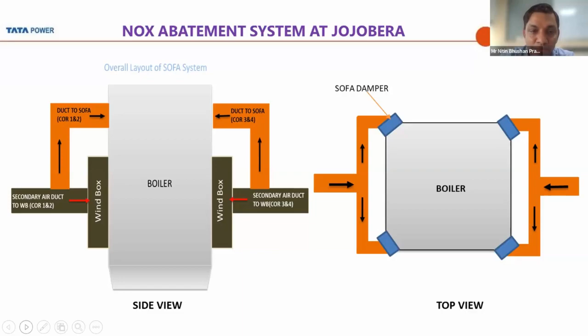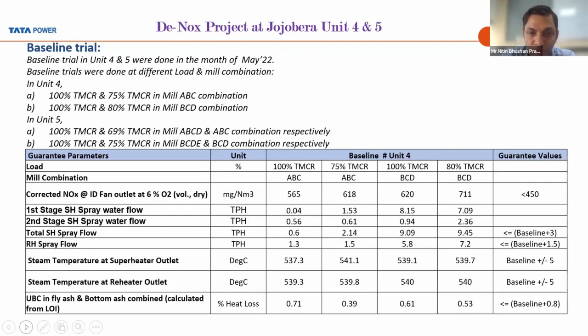This is basically the baseline test that we have done in unit 4 and 5 in the month of May 22. In this baseline test, at full load condition, we did baselines for mill ABC combination and mill BCD combination, and the NOx parameter that we achieved at full load condition: when we take mill ABC in service, it is around 565. At 75% TMCR, it is 618, that is milligrams per normal meter cube. And at 100% TMCR, when we take the top mill in service, that is BCD, it comes to be 620. Basically, the company that has provided it, GE Technologies, has guaranteed a value of less than 450 per Nm cube. Kindly move forward, ma'am.